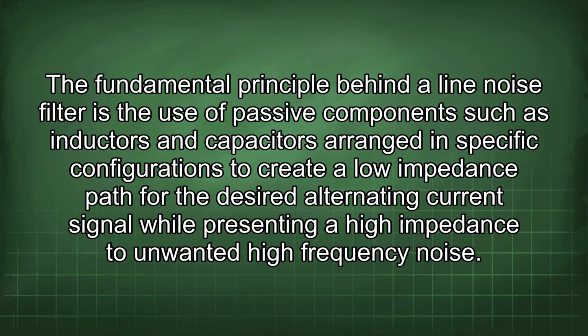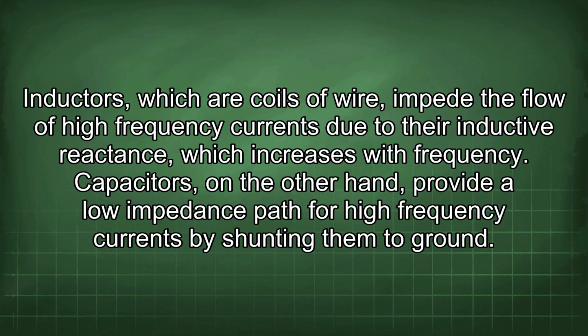The fundamental principle behind a line noise filter is the use of passive components such as inductors and capacitors arranged in specific configurations to create a low impedance path for the desired alternating current signal while presenting a high impedance to unwanted high-frequency noise. Inductors, which are coils of wire, impede the flow of high-frequency currents due to their inductive reactance, which increases with frequency. Capacitors, on the other hand, provide a low impedance path for high-frequency currents by shunting them to ground.